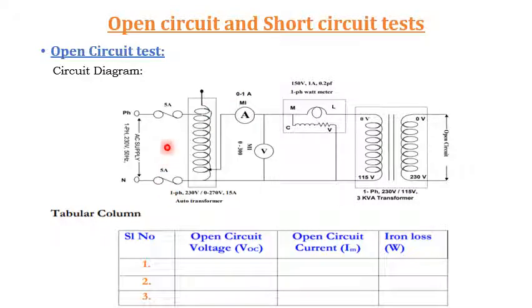Now initially when this switch is closed, the single phase supply is introduced into the autotransformer, then go on varying the voltage with respect to the LV side of the transformer. So it gives the voltmeter reading, that is 115 volt. Then in that case, note down the ammeter reading, which gives the no load current. This is a very small current you can obtain, and no load power can be obtained, and the no load voltage. So these meter readings are tabulated here.